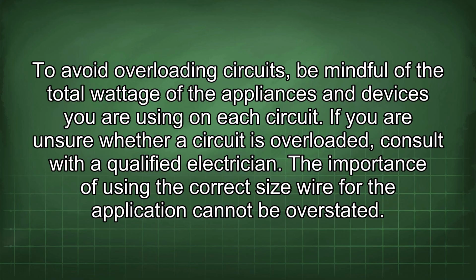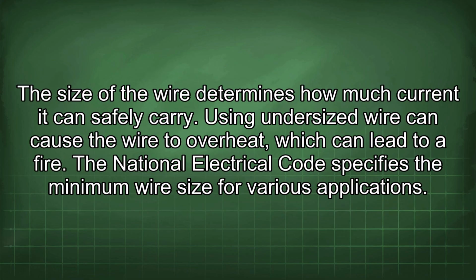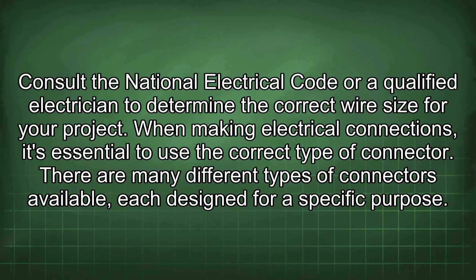The importance of using the correct size wire for the application cannot be overstated. The size of the wire determines how much current it can safely carry. Using undersized wire can cause the wire to overheat, which can lead to a fire. The National Electrical Code specifies the minimum wire size for various applications. Consult the National Electrical Code or a qualified electrician to determine the correct wire size for your project.